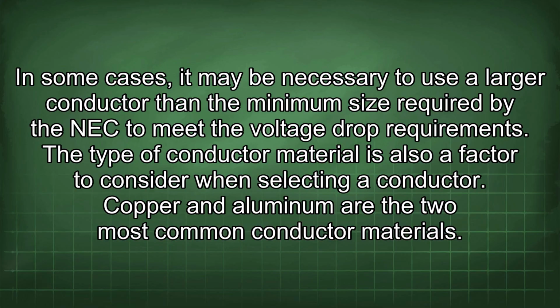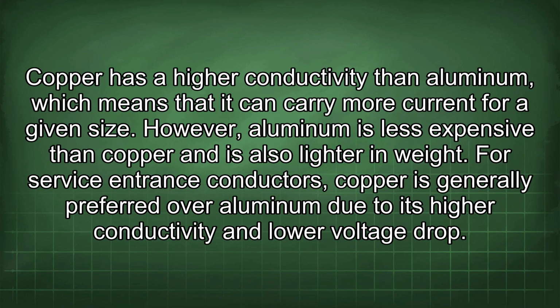The type of conductor material is also a factor to consider when selecting a conductor. Copper and aluminum are the two most common conductor materials. Copper has a higher conductivity than aluminum, which means that it can carry more current for a given size. However, aluminum is less expensive than copper and is also lighter in weight.